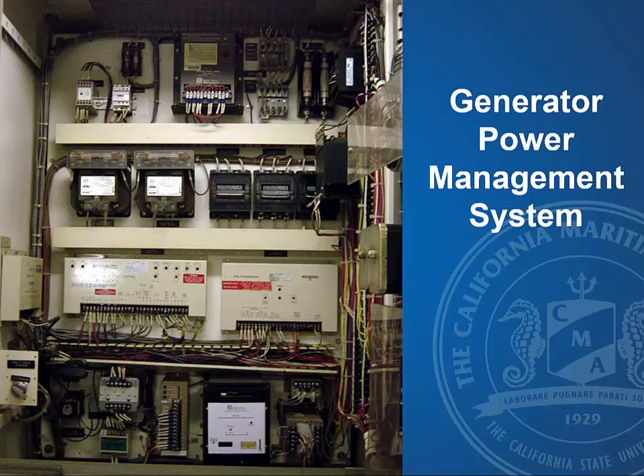On the Bear, you do have a power management system, but we elect typically not to use it. It uses a Woodward system that is in the main switchboard. And this system is perfectly capable of putting generators on and off, synchronizing them, paralleling together, all with no human intervention.